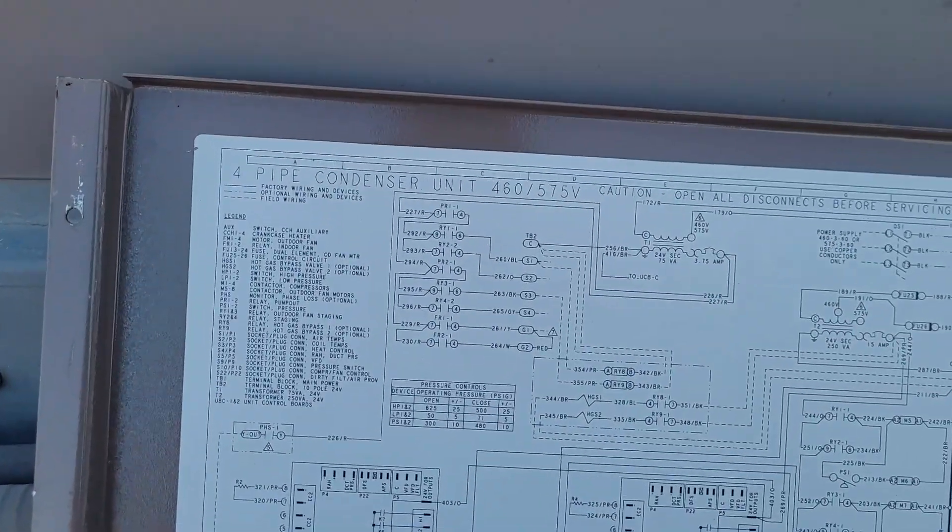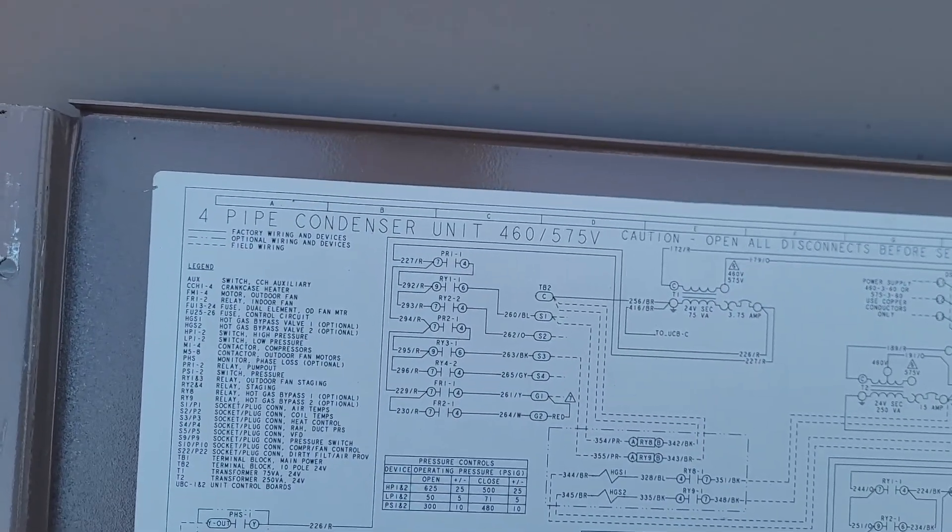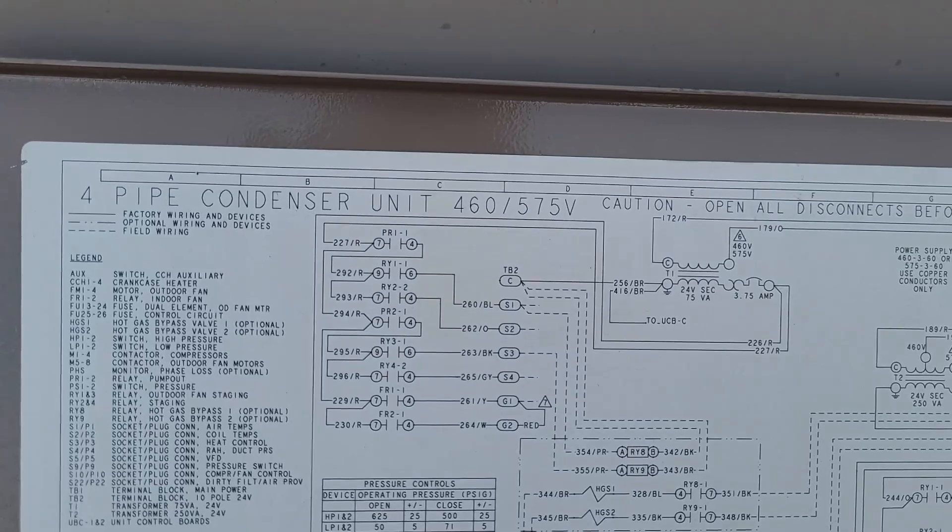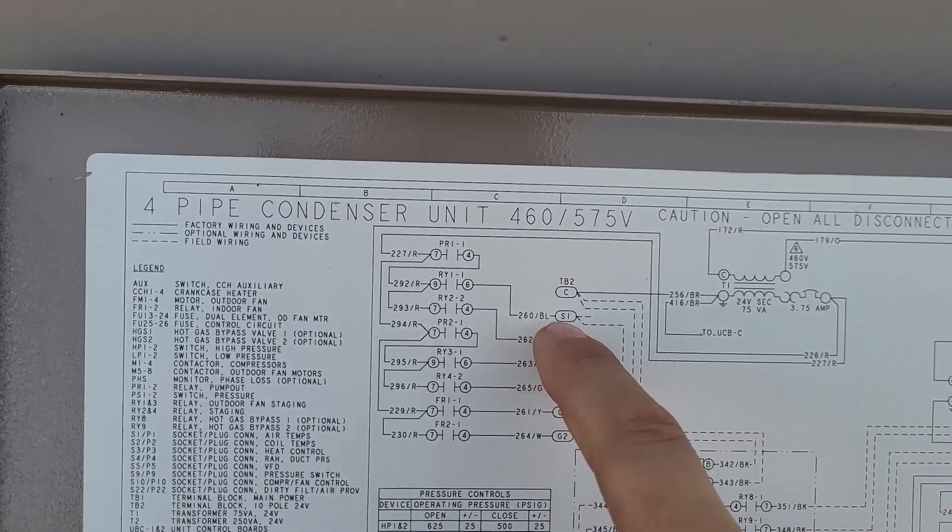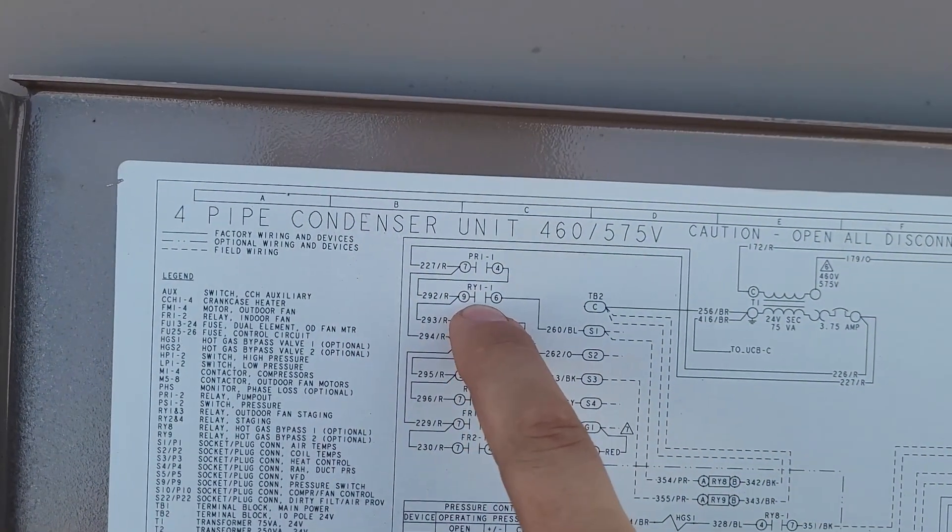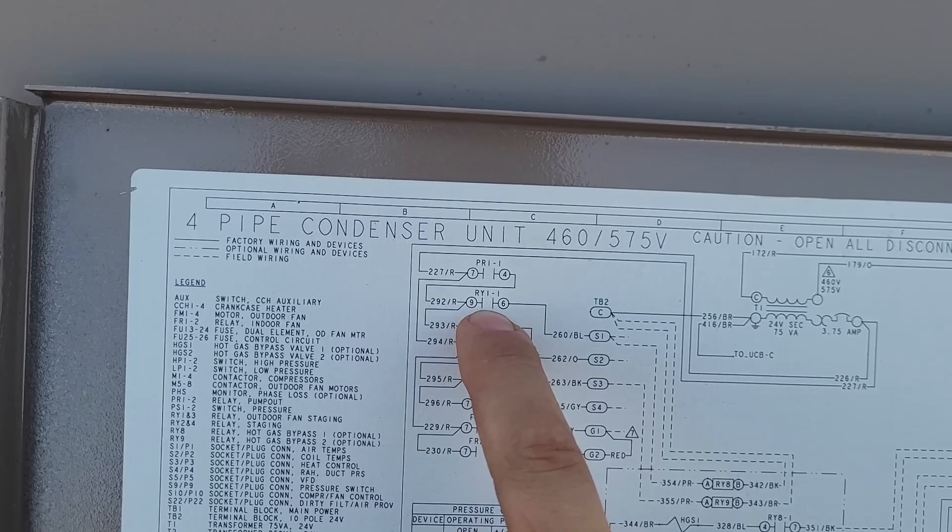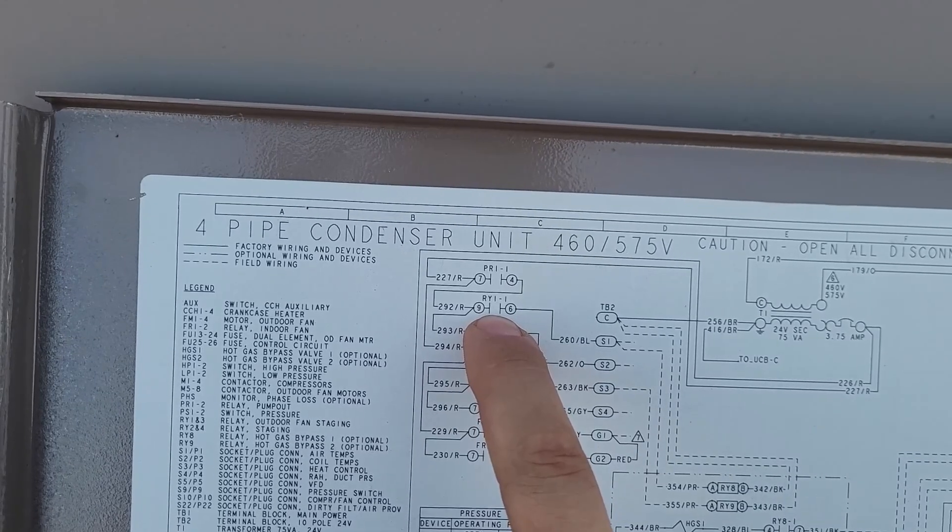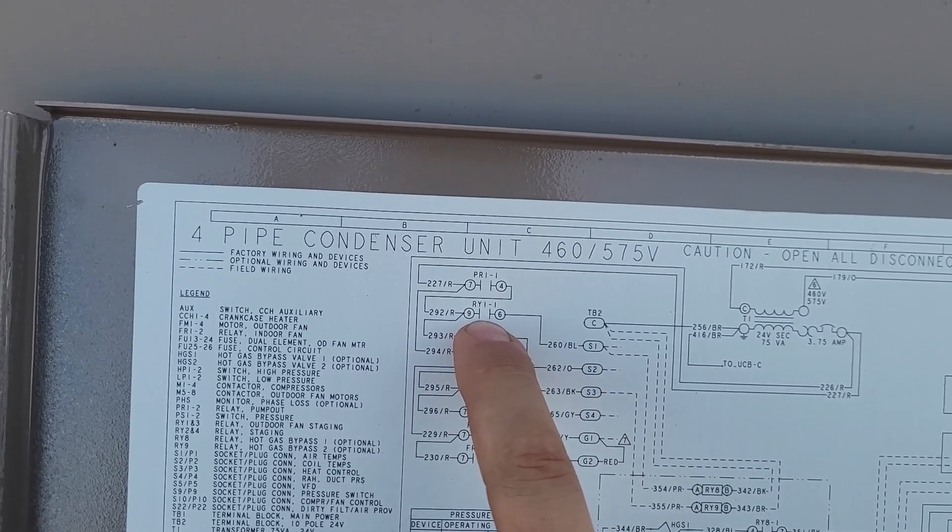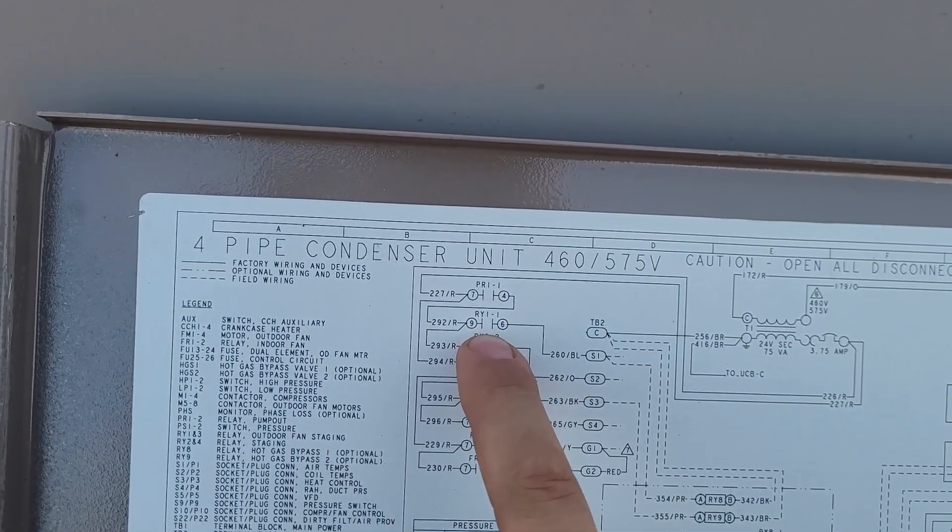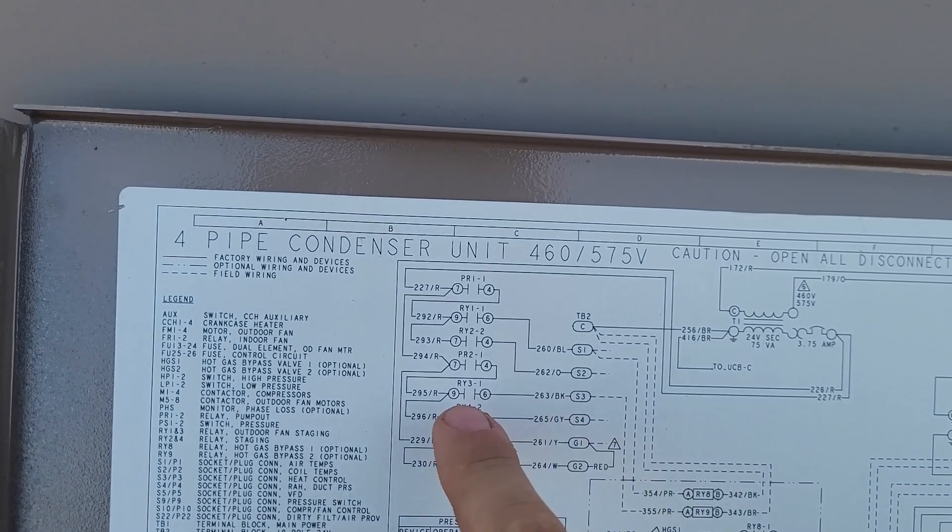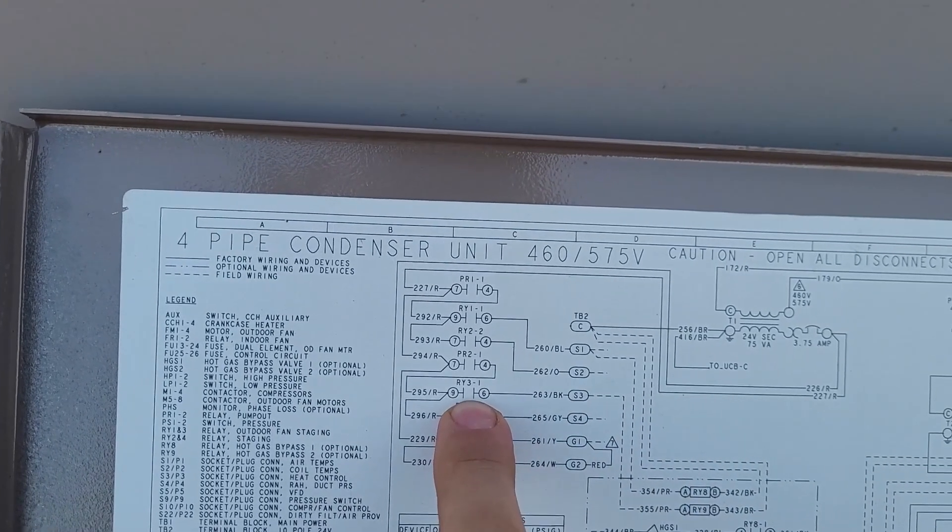So I trace the wires up here, and they go to S1 and S3. So here's S1, it gets its power from a dry contact on the relay RY1, and then S3 is the same thing on RY3.